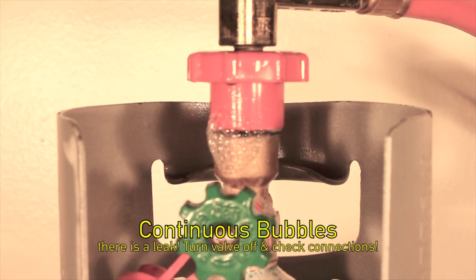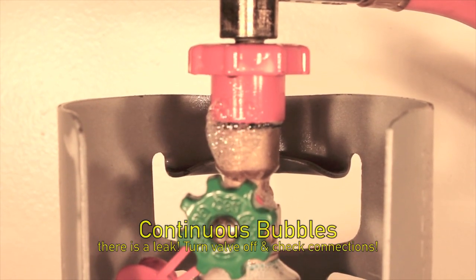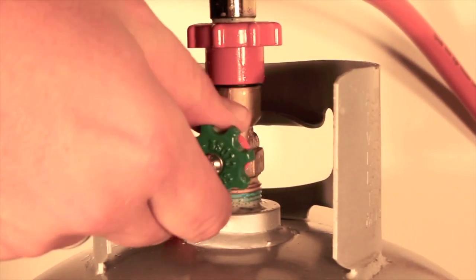If you see continuous bubbles forming, this means you could have a leak. Proceed then to turn off your cylinder valve and re-tighten your connections. Then to be safe, redo the leak test.